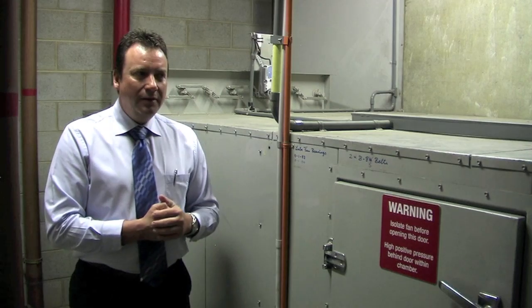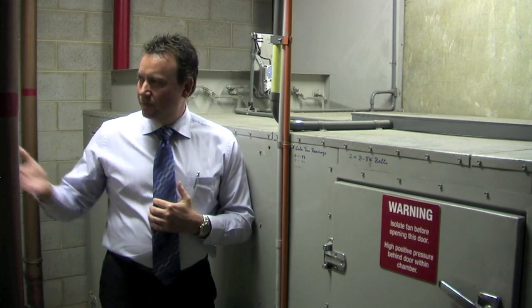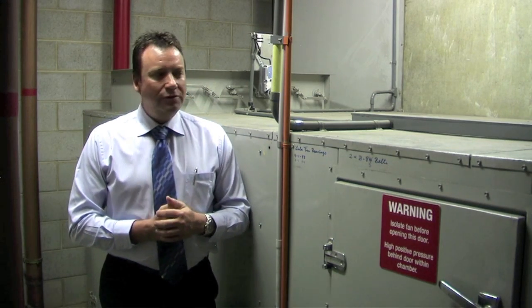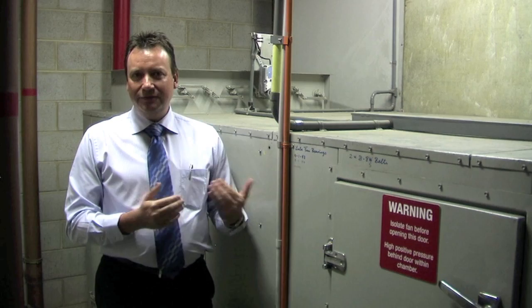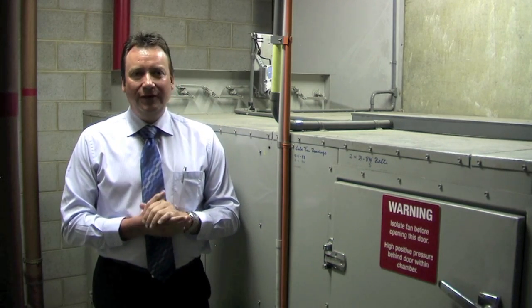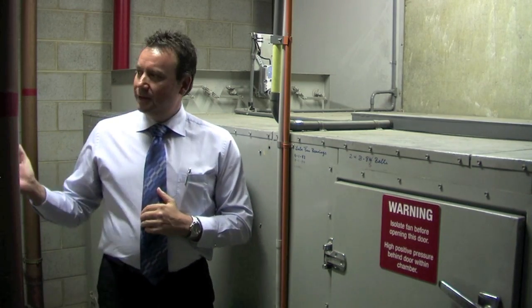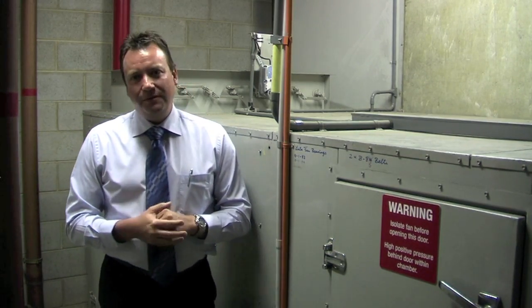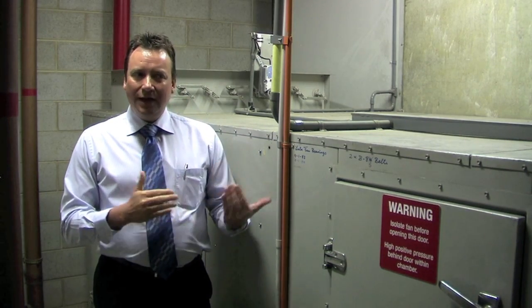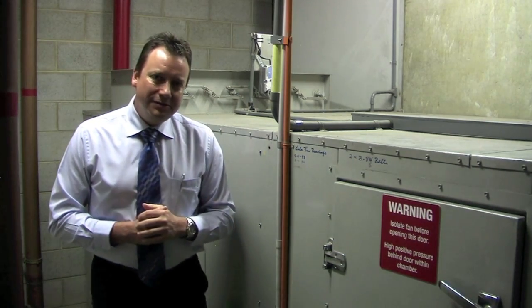The retrofit was done over a long weekend. Prior to the retrofit we installed data loggers to the switchboard, which gave us a month's worth of energy logging data, establishing the current to be around the 8 amp mark over the three phases. After the retrofit we put our data logger on the board again for another month and highlighted a consistent energy saving. We had about a 4 amp consumption, therefore we achieved about a 50% power saving.